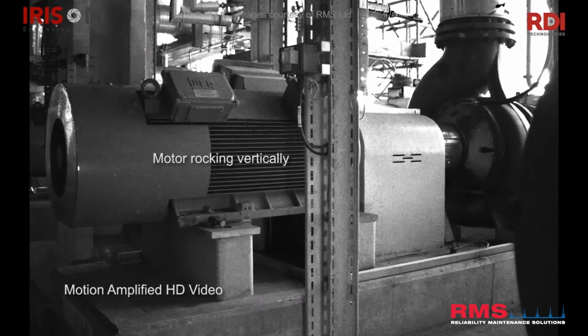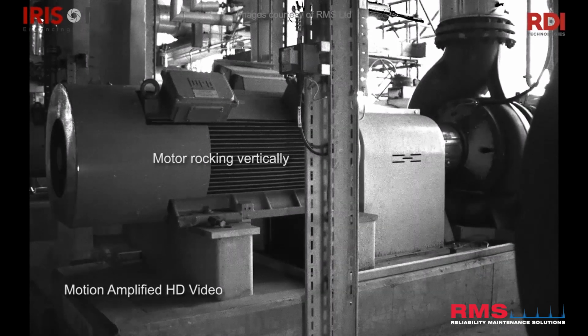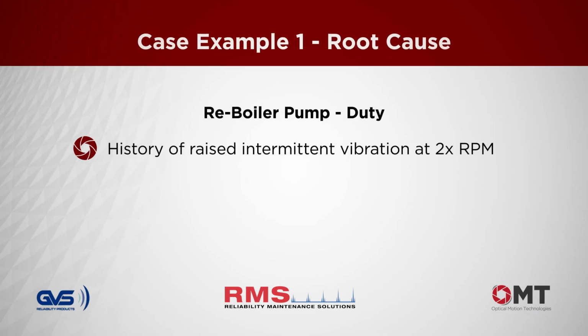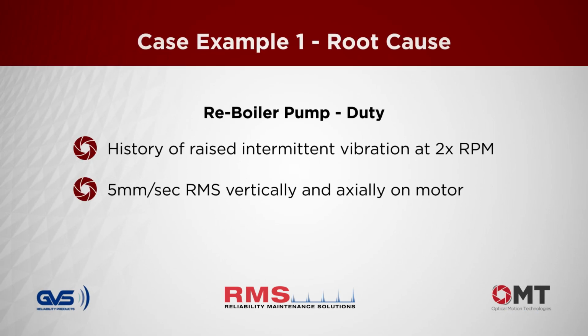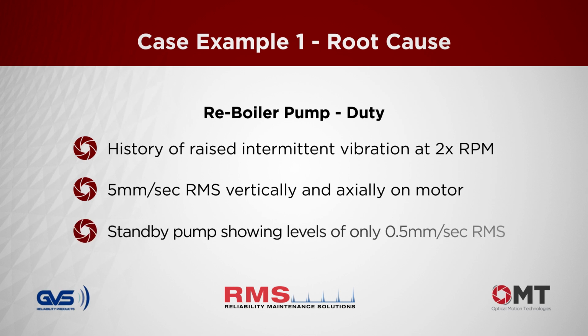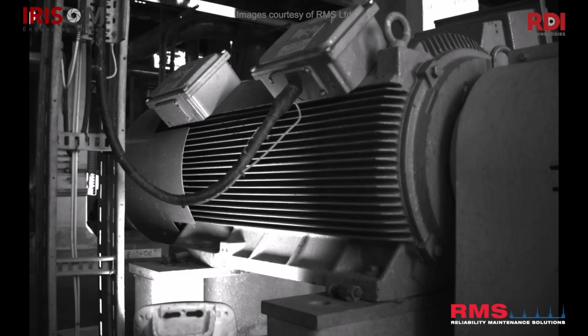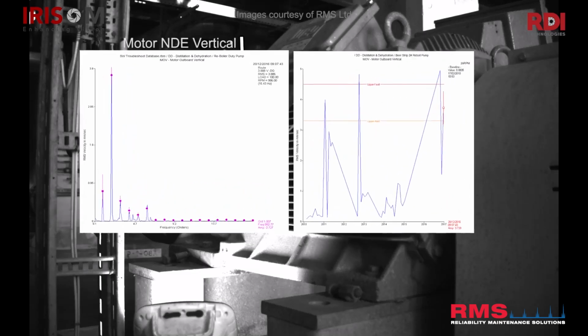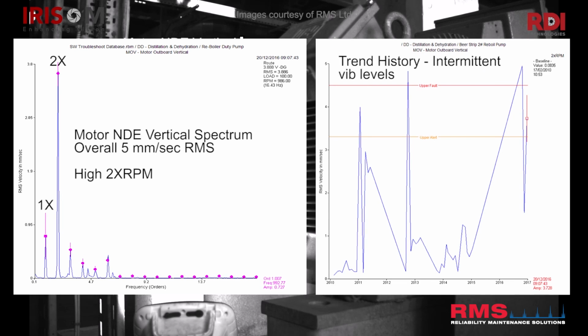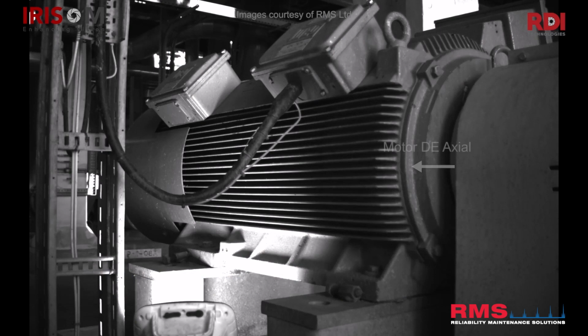Misalignment, or is it? The duty reboiler pump had a history of raised 2 times vibration, 5 mm per second RMS vertically and axially on the motor, typical of misalignment. The standby pump was showing levels of only 0.5 mm per second RMS. The unacceptable vibration levels were detected via the periodic condition-based monitoring measurements as part of the predictive maintenance program.